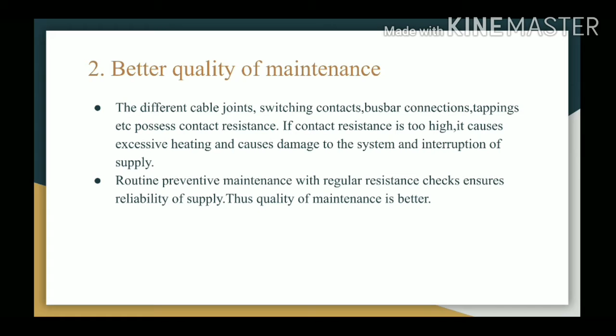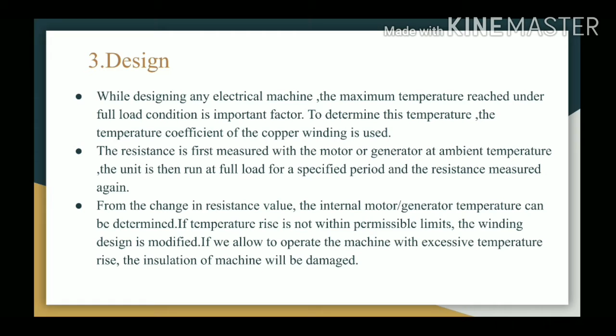Third is design. While designing any electrical machine, the maximum temperature reached under full load condition is an important factor. To determine this temperature, the temperature coefficient of the copper winding is used. The resistance is first measured with the motor or generator at ambient temperature. The unit is then run at full load for a specified period and the resistance measured again. From the change in resistance value, the internal motor or generator temperature can be determined. If temperature rise is not within permissible limits, the winding design is modified. If we allow the machine to operate with excessive temperature rise, the insulation of the machine will be damaged.